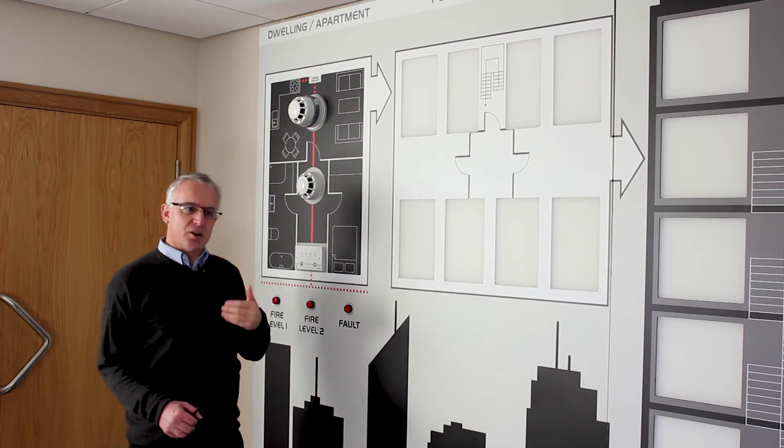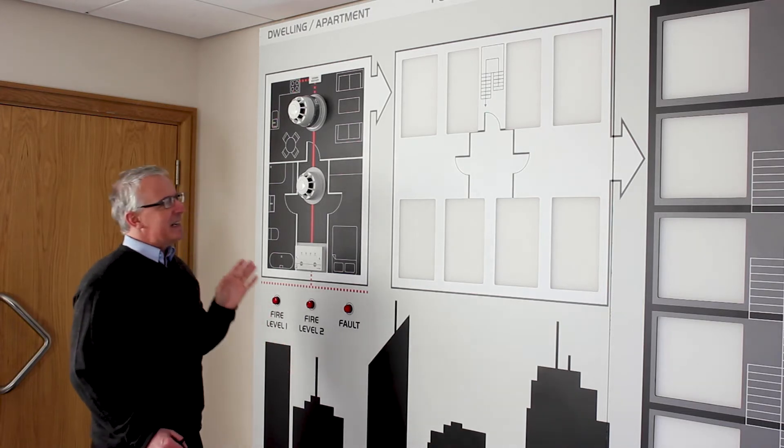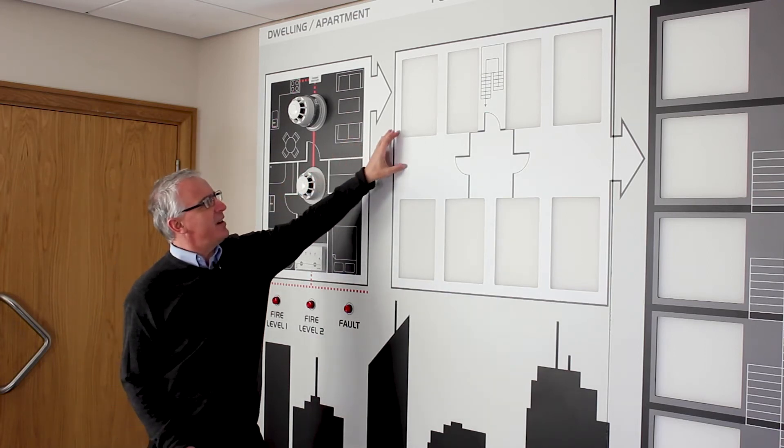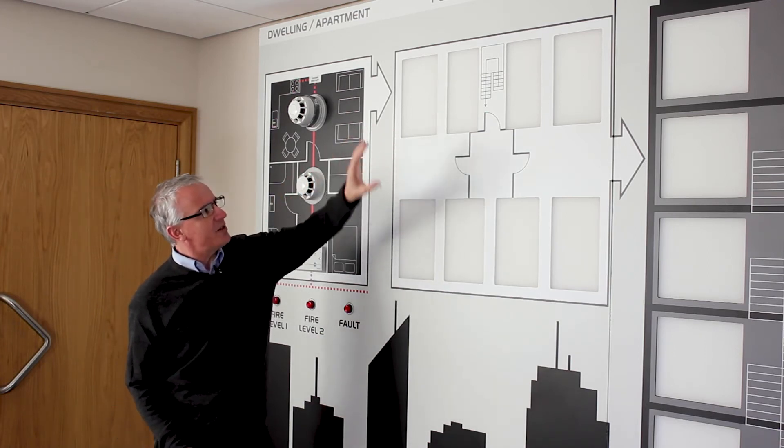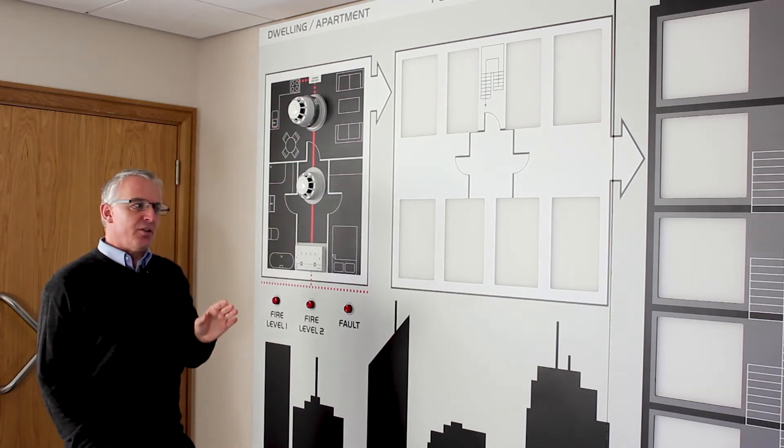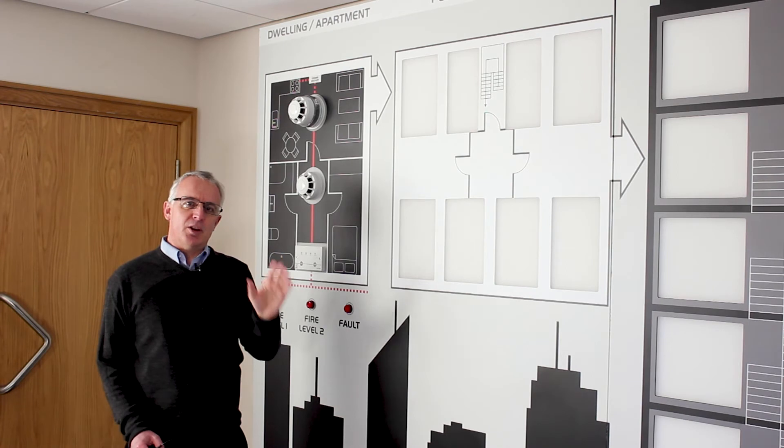We can regard that as a confirmed alarm signal, and in such situations would it not make sense if the fire was in this particular dwelling to warn other dwellings on that floor that there's a fire? Well, using the cause and effects on the landlord panel, we can do just that.